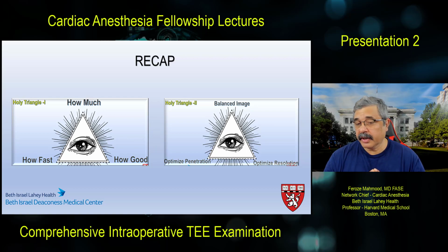The holy triangle number 2 is based on how deep or how superficial you want to see, or a balanced image. When you want to optimize penetration, which means you want to see very deep into the tissues, you use a lower frequency or longer wavelength transducer, compromising somewhat on the resolution. And if you want to optimize resolution, or you want to see something superficial, then you use a higher frequency transducer with a shorter wavelength, and of course, you wouldn't be able to see structures deeper into the tissues.